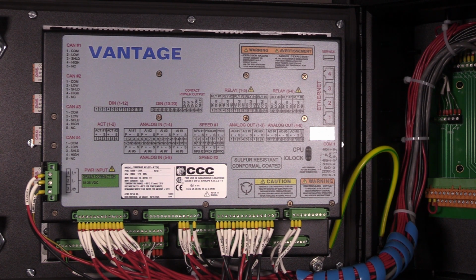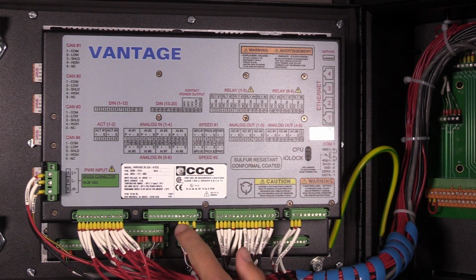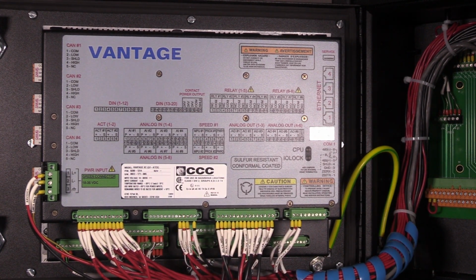The discrete input channels are designed for use with 24-volt DC signal. These signals designate on or off from an end device, such as a button or switch. An isolated contact power voltage supply of 24 volts DC is provided to use with the discrete inputs that require it. This supply includes a short circuit and overvoltage protection. Do not use the contact power output to power any other devices. The contact output power on pins 21, 22, and 23 could supply up to 150 mA maximum.